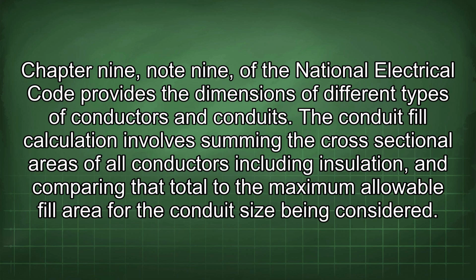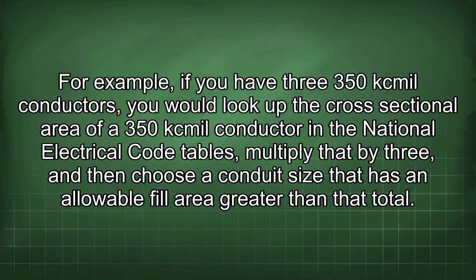The conduit fill calculation involves summing the cross-sectional areas of all conductors, including insulation, and comparing that total to the maximum allowable fill area for the conduit size being considered. For example, if you have three 350 kcmil conductors, you would look up the cross-sectional area of a 350 kcmil conductor in the National Electrical Code tables, multiply that by 3, and then choose a conduit size that has an allowable fill area greater than that total.